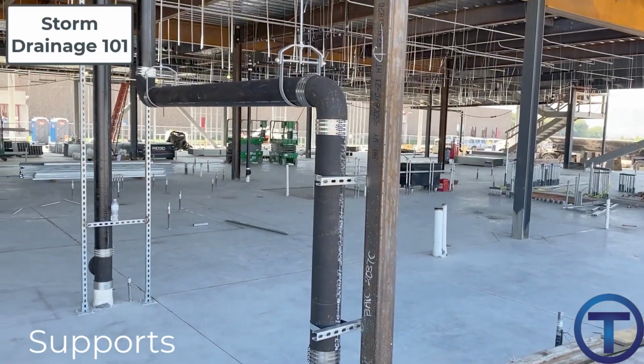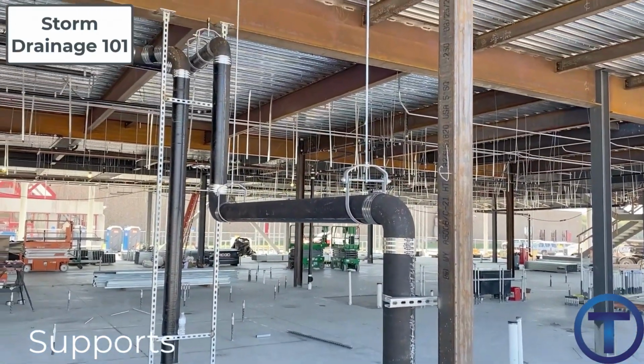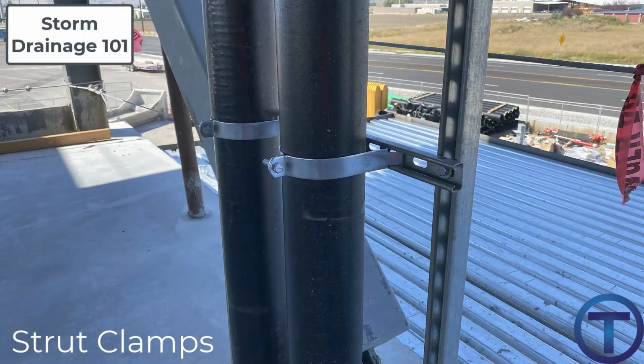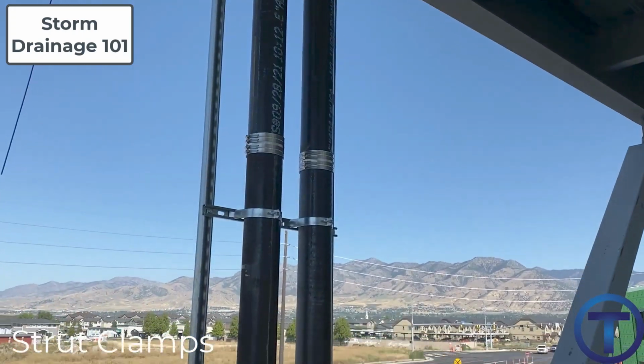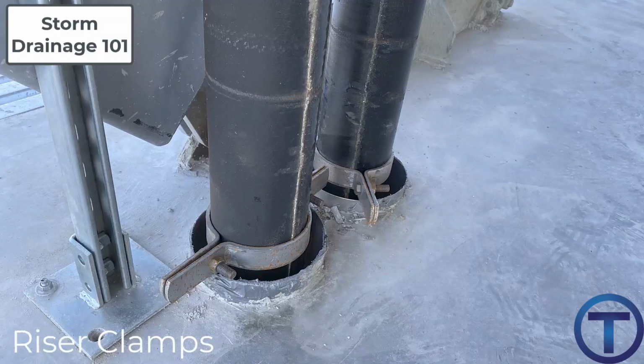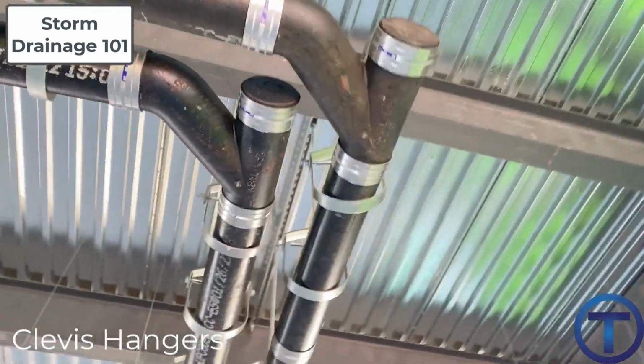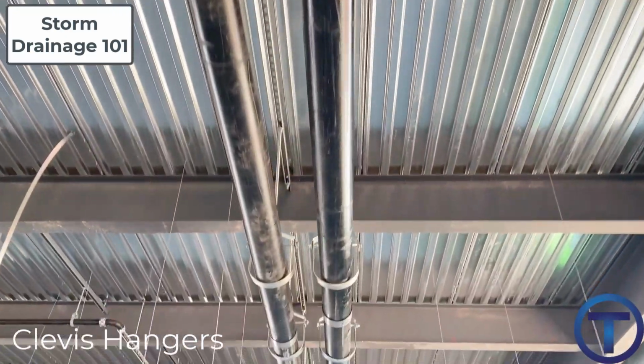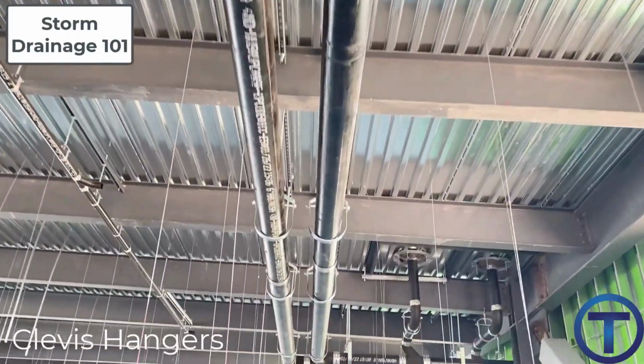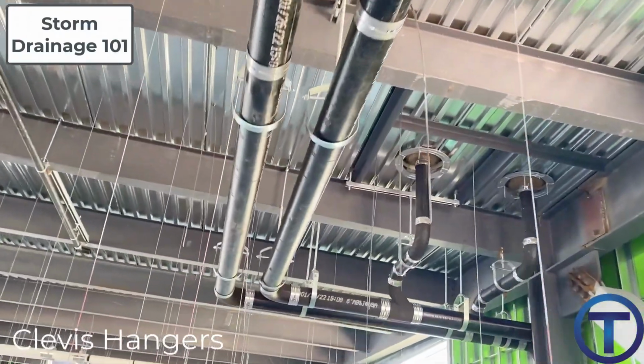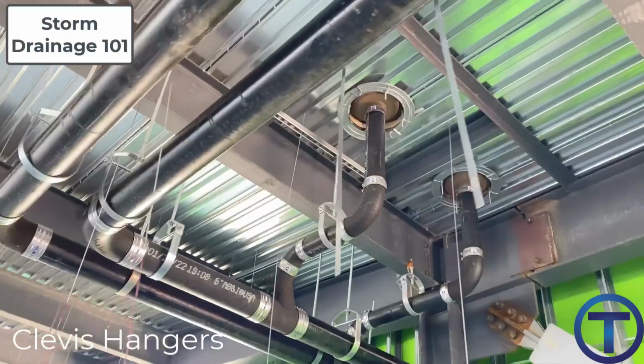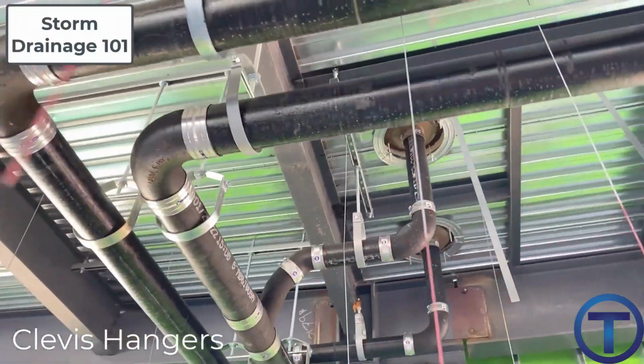Roof drains are supported using your typical pipe support means. Very often in commercial settings, we're going to see the use of strut and strut clamps, and there's any variety of ways you can put that together to help hold up the pipe. Riser clamps are going to be helpful to hold those vertical roof drain pipes in place as they pass from one floor to another. And of course, all thread and Clevis hangers are going to be a very common way of hanging all of these roof drains and supporting them properly. They are supported just like any other drainage pipe at the given intervals that code would require.